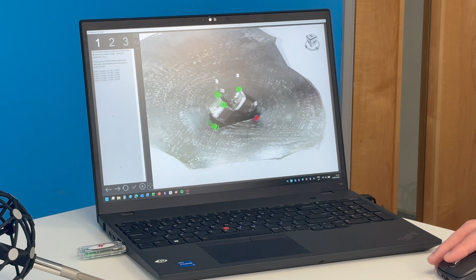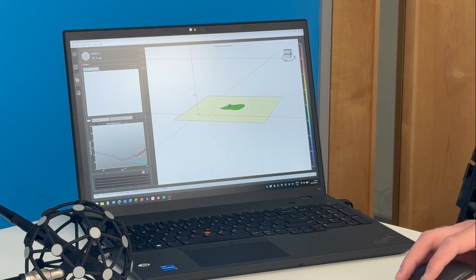Here we can see the real-time spectrum of the probe. We can whistle to make sure everything's working correctly. We see that the sensor recognizes the acoustic sound. We then need to set up our DAC sensitivity. This is dependent on the source. So now we turn on our source and we can start the captures.